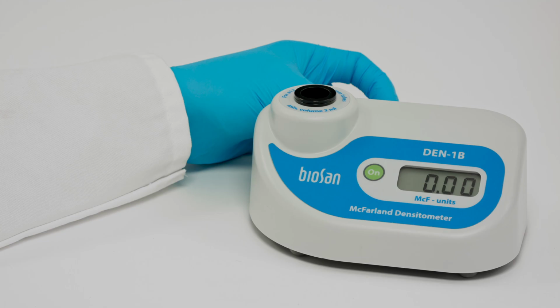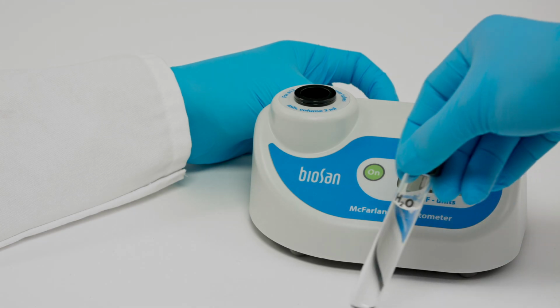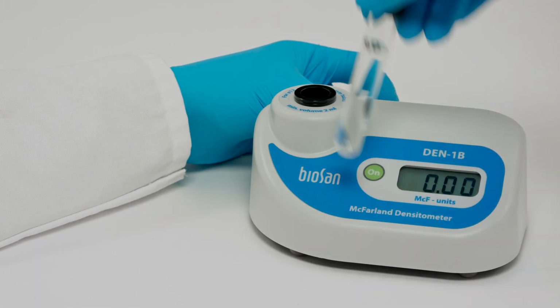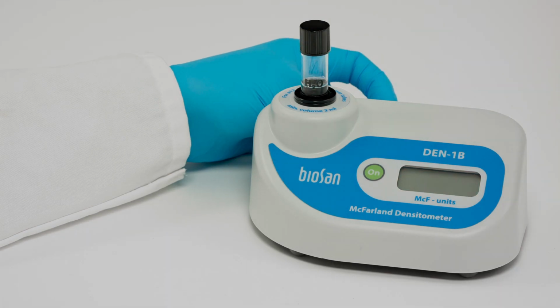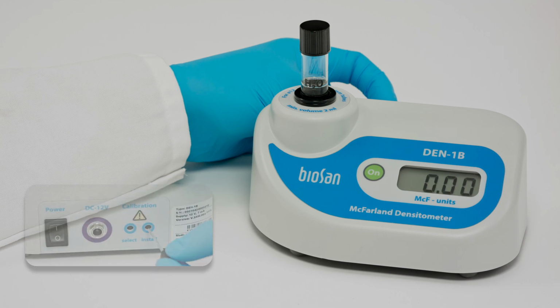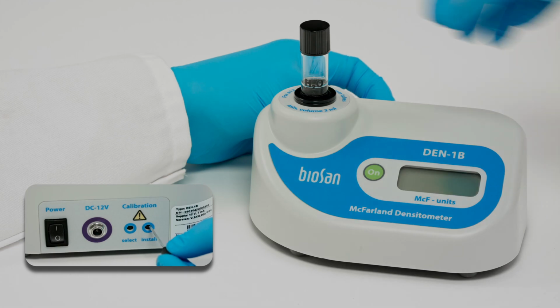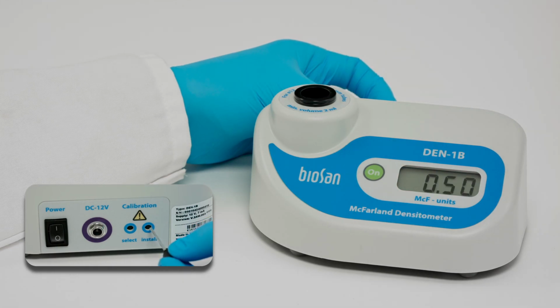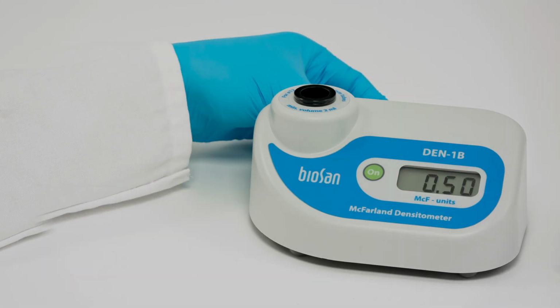Display shows 0 indication. Insert standard for 0 value into the socket of the unit. Before placing the standard, gently mix the standard like shown in this video. If the standard for 0 value is not available, fill the tube of the kind that is used for your operations with distilled water. Press Install button to save the 0 value standard. Display shows next required calibration value.